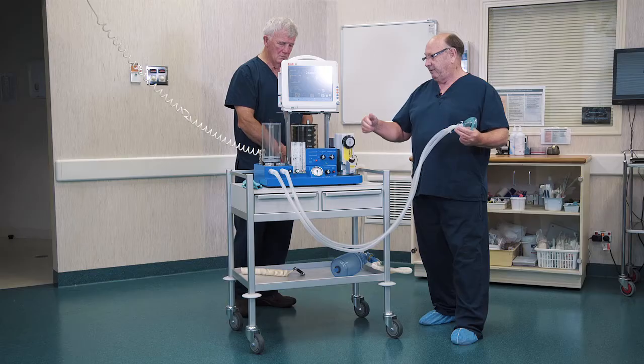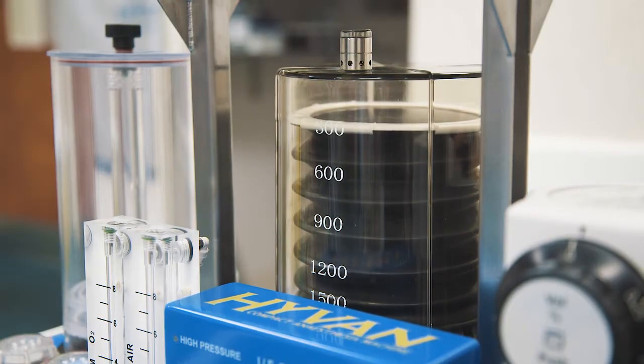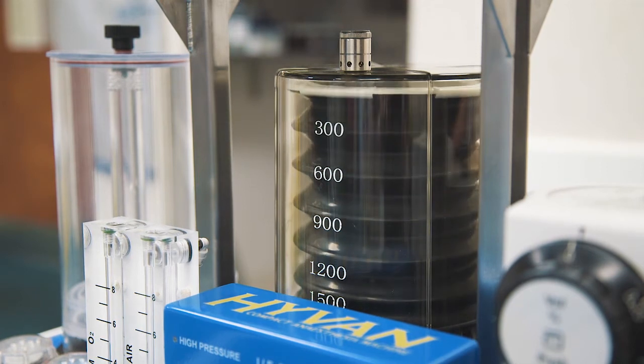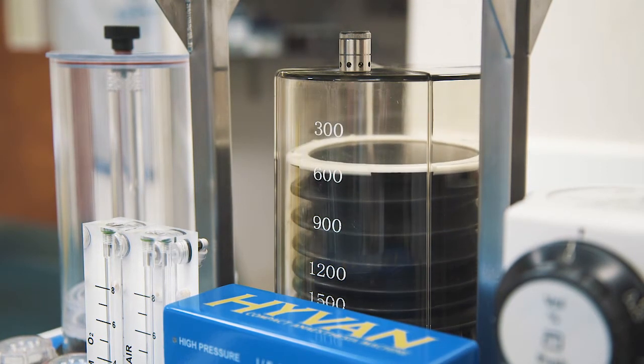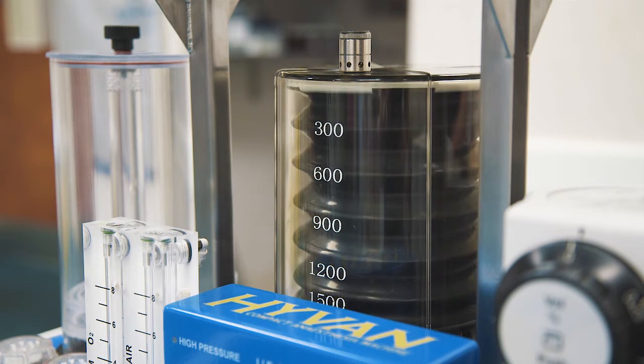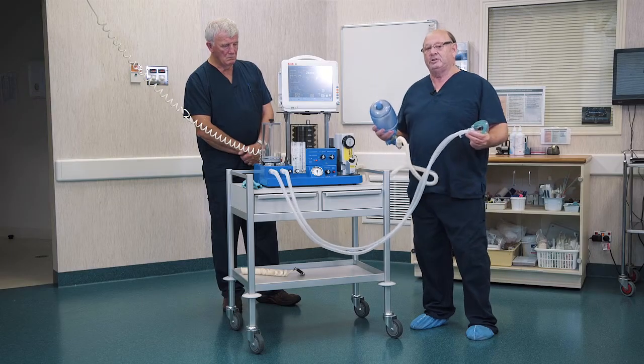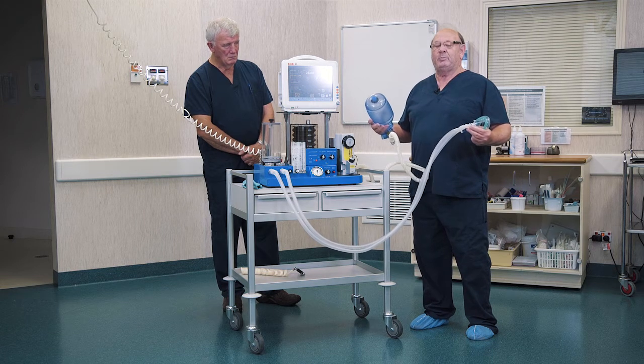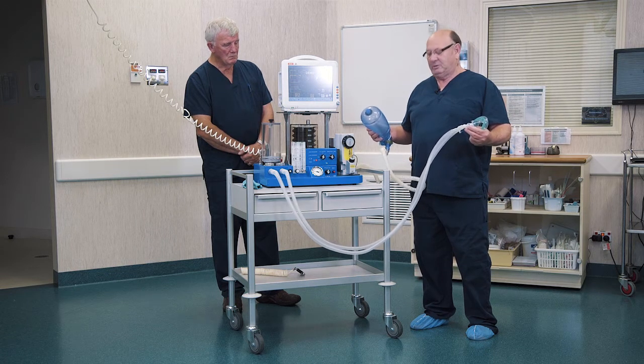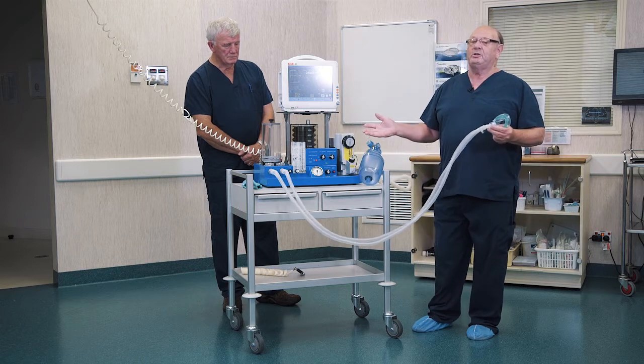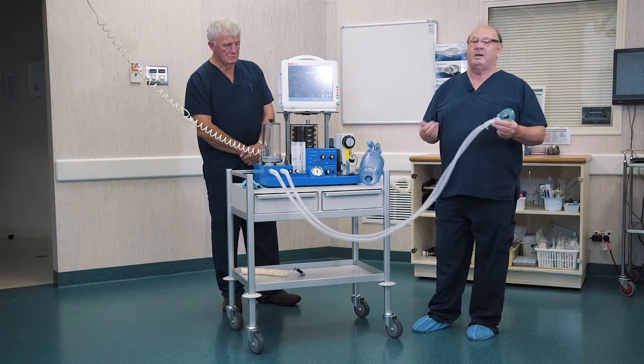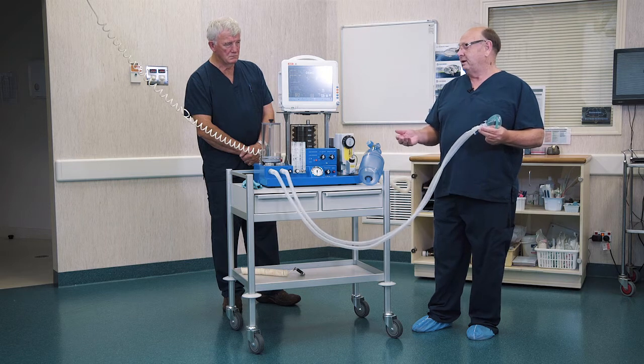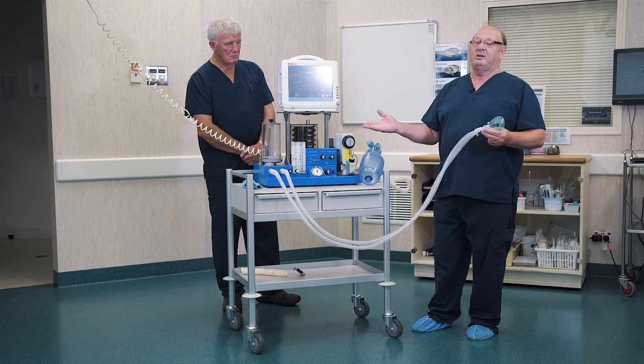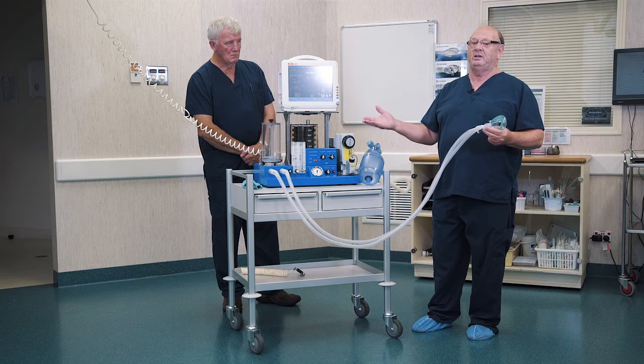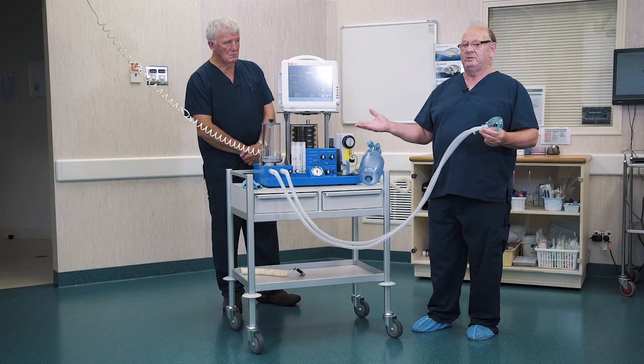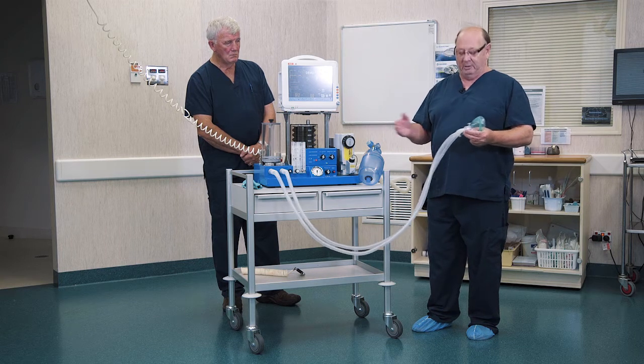From the vaporizer, the mixed gas then enters into the sodalime absorber and the bellows here, which is basically the patient bag. It has no APL valve on this machine. In fact, when you squeeze the self-inflating bag, which is attached to it, it locks up the bellows and sends gas to the patient. The patient can also breathe spontaneously, and I'll just put this mask on and show you how that works. And you can see that the bellows then acts like a small spirometer, so you can actually see how much volume the patient is breathing if you don't have a monitor.